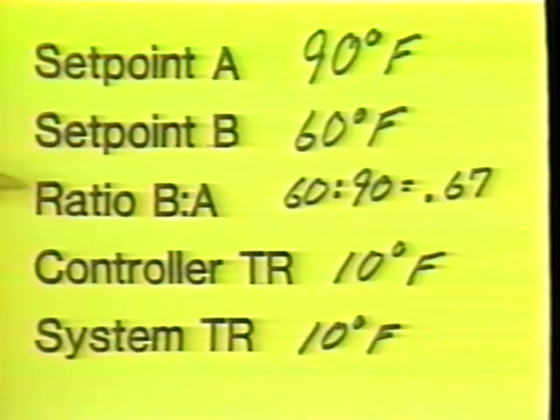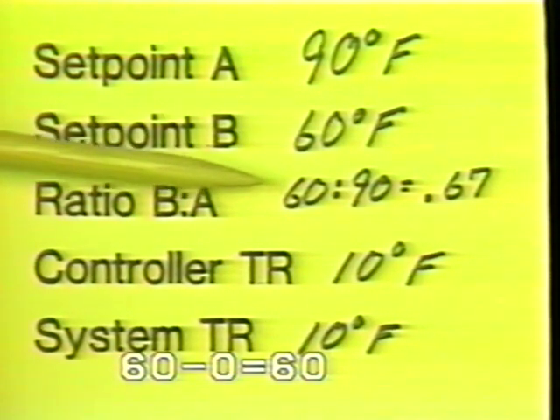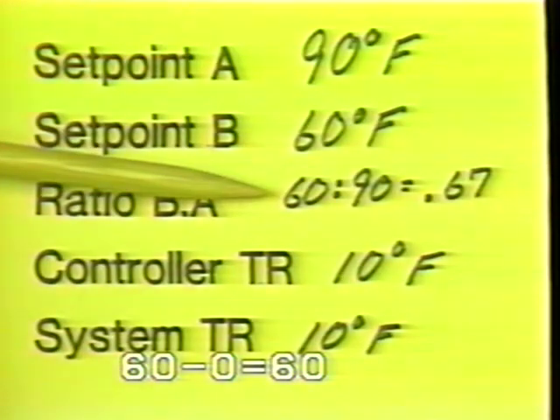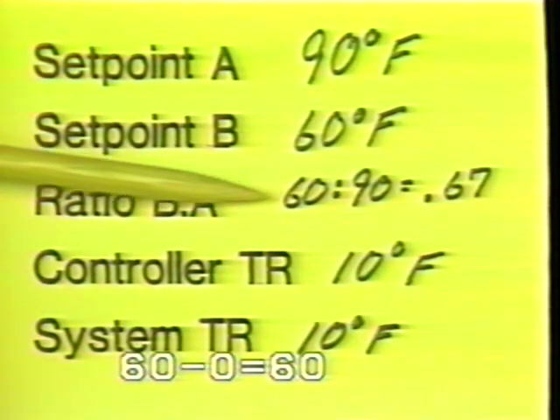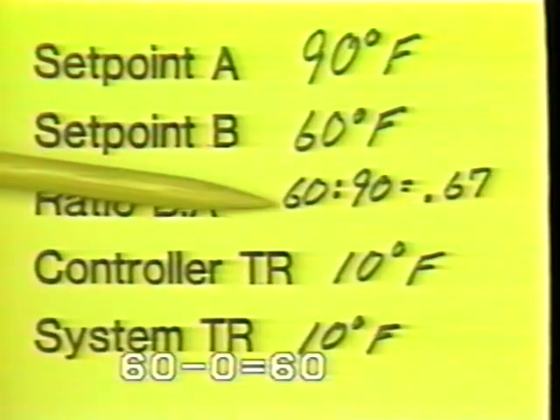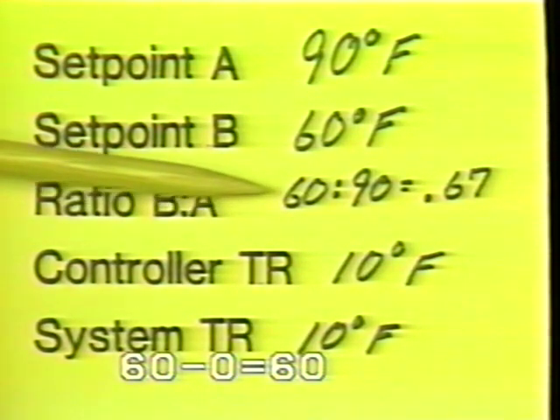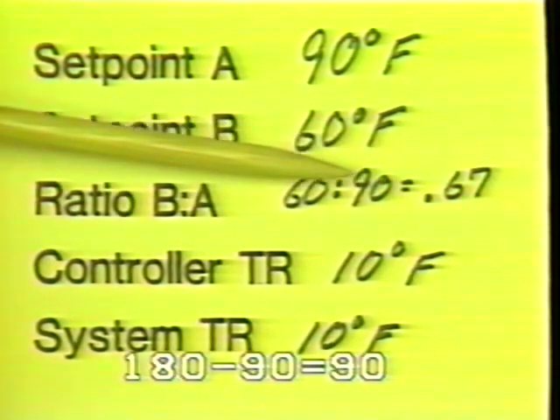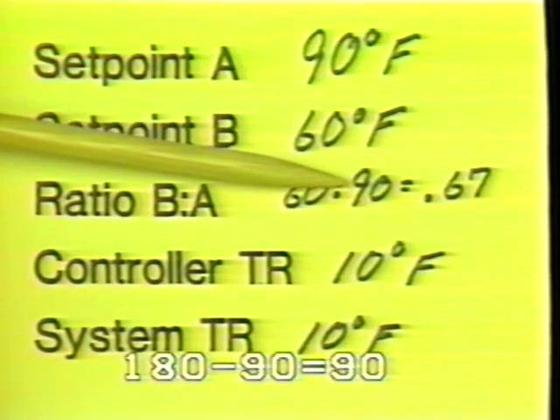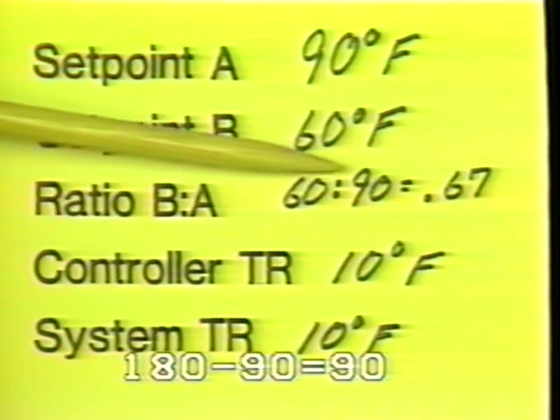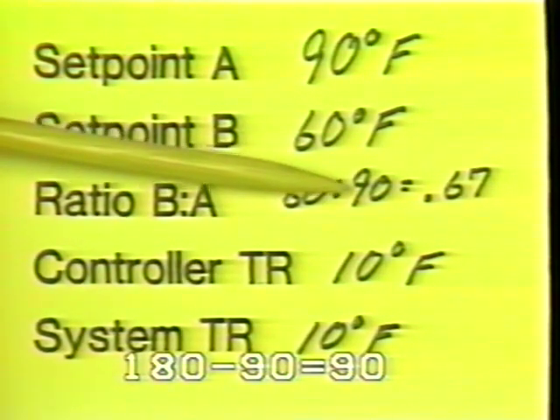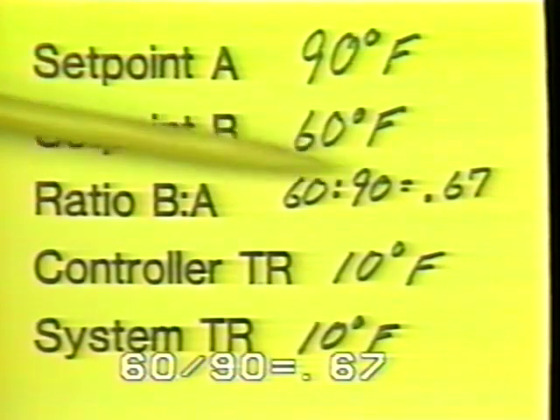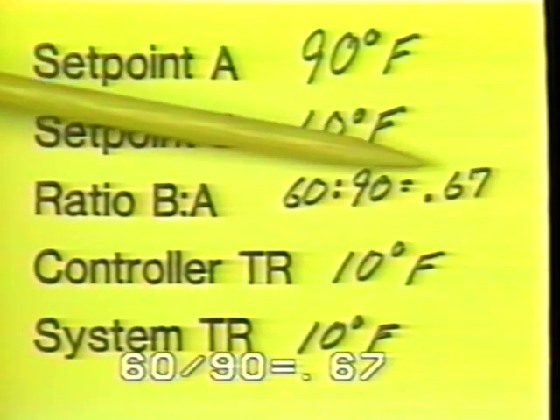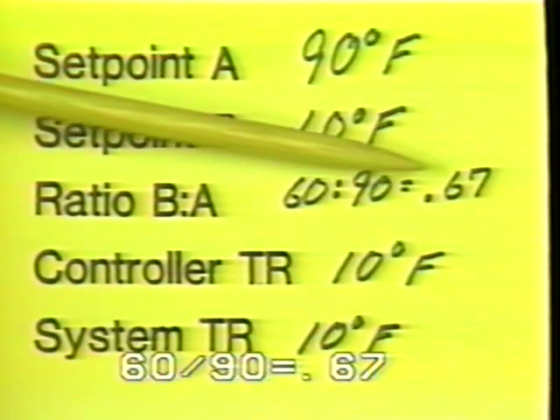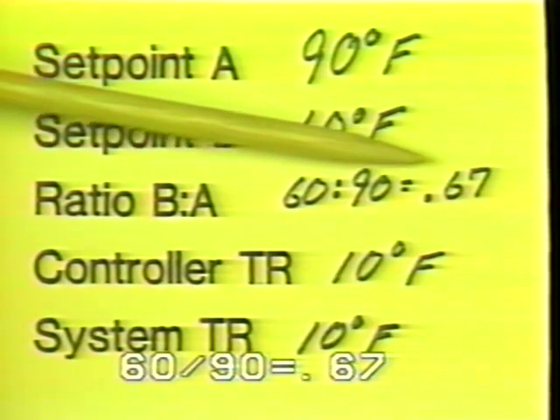In this case, the change in variable from the design temperature to the fade-out temperature for the outside air was from 0 to 60 degrees, a change of 60. The change at A was from a design hot water temperature of 180 down to 90, a change of 90 degrees. Our ratio then is 60 to 90, or 0.67. We would adjust the ratio dial to read 0.67.